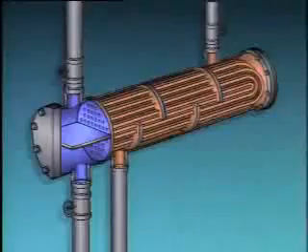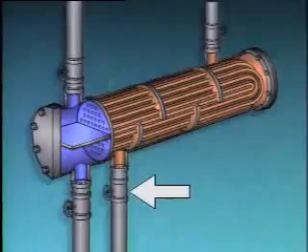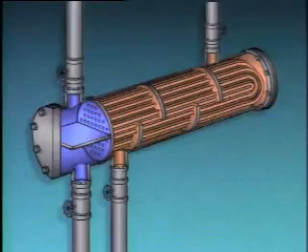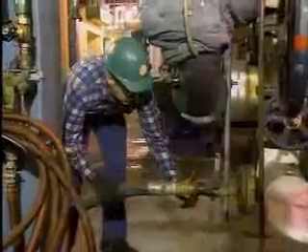The operator then shuts the shell side inlet valve. On the heat exchanger shown in this example, the shell side has no isolation valve on its outlet. Some shell and tube heat exchangers have an isolation valve on this outlet. With those heat exchangers, the isolation valve must be shut to completely isolate the heat exchanger. After the isolation valve is shut, the operator opens the cooling water drain and vent valves. Once all of the fluid is drained from the heat exchanger, the operator closes the vent and drain valves to complete the shutdown.